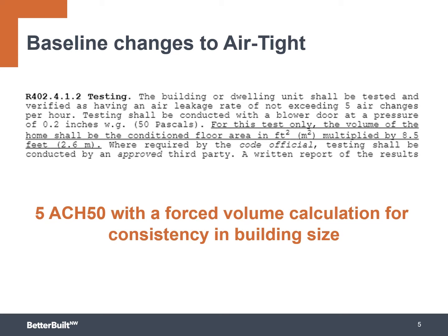That didn't feel quite right to us — it doesn't really sit right. It has to do with the shape and size of homes and the dimensionality, in other words the difference between conditioned floor area and volume. So we wanted to get it a little bit corrected so that small, medium, and large homes all have the same chance, with the same degree of air sealing, to meet the tightness requirements. A small change has been made to how they do the calculation — basically, they force a uniform ceiling height to be adopted, and that helps level things out a bit.